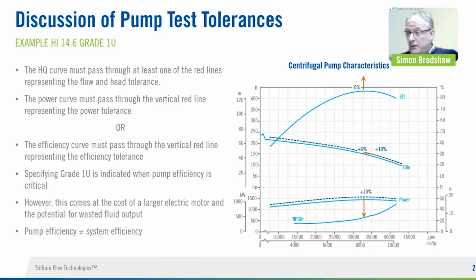Now, if you can handle that additional head and flow going through your system, if you can handle it in an efficient way, then great. You can specify 1U and you're good to go. But if all you're going to do is essentially take that energy that the pump has put into the fluid and then break it down across some pressure control valve, you've essentially put a lot of energy efficiently into the fluid for no benefit. So it is very important that you consider both, if you're targeting ultimate efficiency, that you specify the right grade for the pump, but also that your system can handle it in an appropriate way. Otherwise, as I said, you're kind of wasting your time here a little bit. Next slide, please.